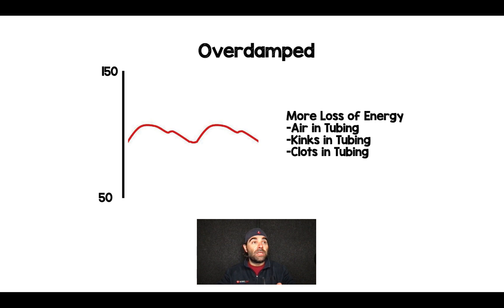Now, there are two things that can happen that can give you false readings on an arterial line. One is called over-damping and the other one is called under-damping. All damping means on an arterial line — think of it as a shock absorber, like shocks on a car when you're going over a bumpy road. There are things that will make the shocks work better and there are things that will make them work worse.